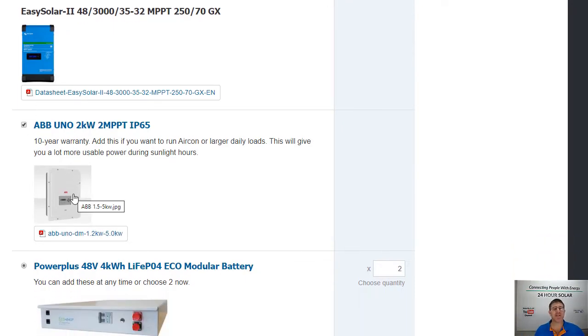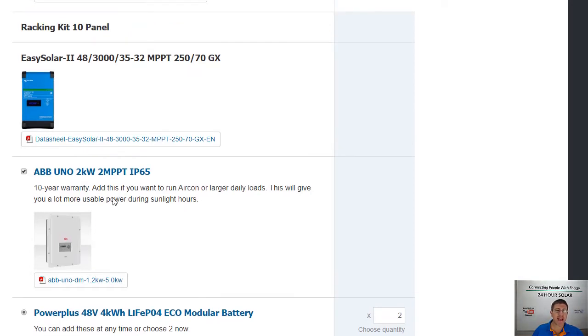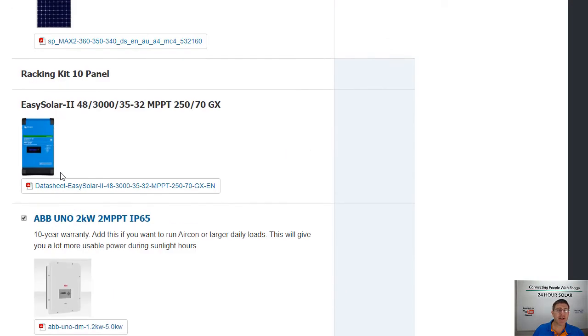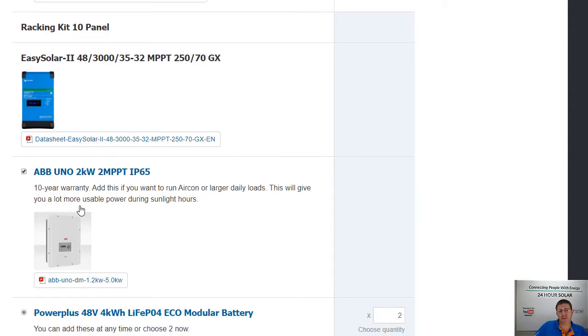Adding these grid connected inverters is a lot more efficient for daily loads. So if you plan to run air conditioning or anything heavy during the day when the sun's out, these are a great option because they're actually more efficient too. There's about 5% losses from your panels to the usable power at your power point when using an AC coupled or grid connected inverter, compared to taking panels to batteries and pulling it back out to your power point, where you can lose 20 to 30% efficiency. So off-grid, if you're thinking about using a lot of energy during the day, it's worth considering whacking in one of these AC coupled inverters.